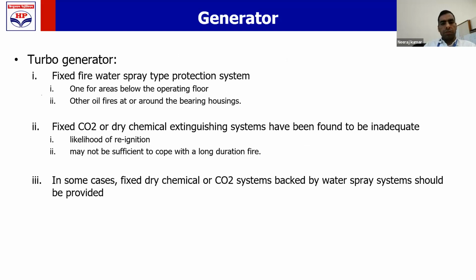Now, how should the firefighting equipment for a turbine generator be? Generally, a turbine generator comes with both a fire detection system as well as a firefighting system. In many cases a CO2 flooding system is given as the firefighting system, but this standard requires a fixed fire water spray system, not CO2 flooding. A fixed fire water spray system shall be provided for the gas turbine generators.